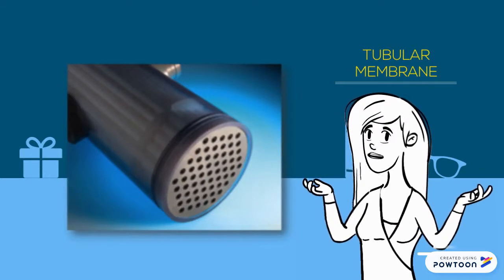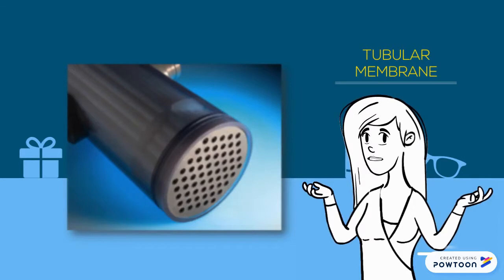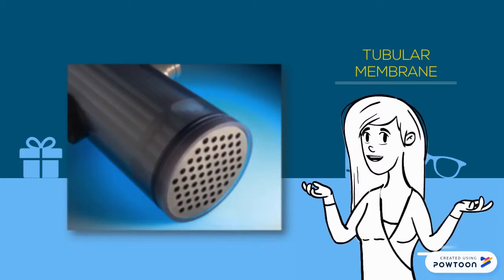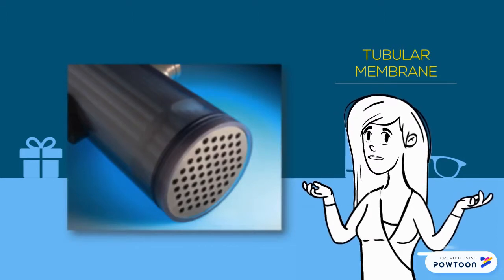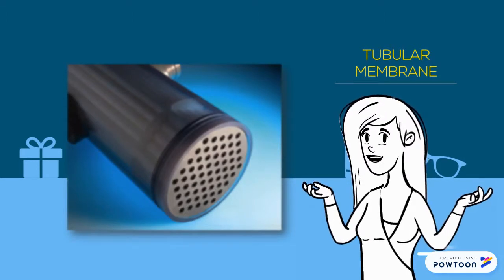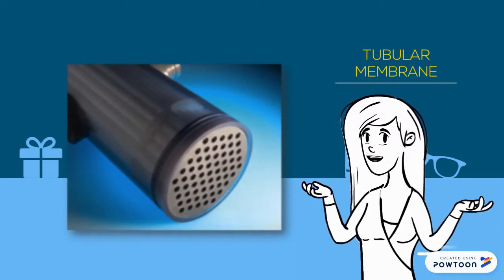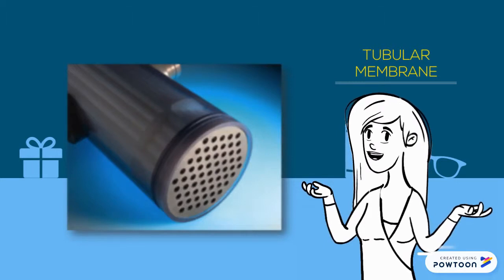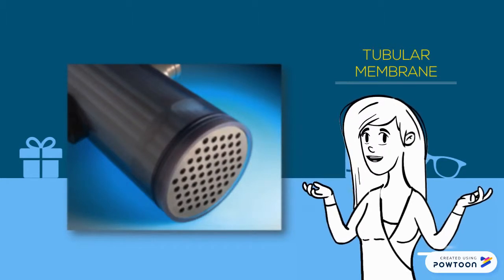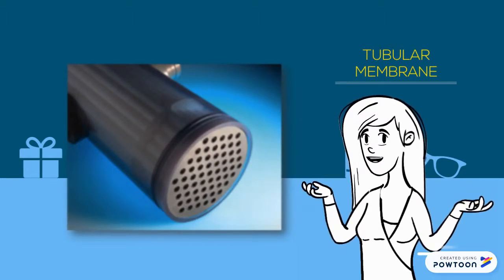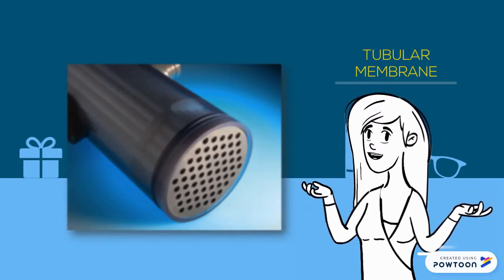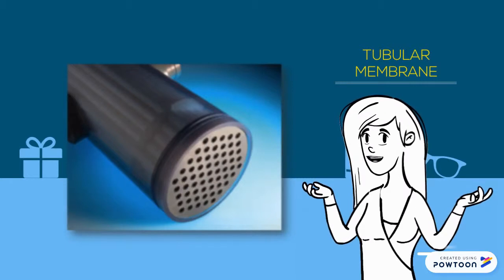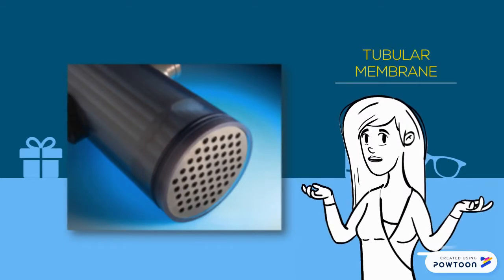Tubular membrane modules are tube-like structures with porous walls. Tubular modules consist of a minimum of two tubes: the inner tube called the membrane tube, and the outer tube which is the shell. Tubular modules work through tangential cross-flow and are generally used to process difficult feed streams such as those with high dissolved solids, high suspended solids, and lipids such as oil, grease, and fats.